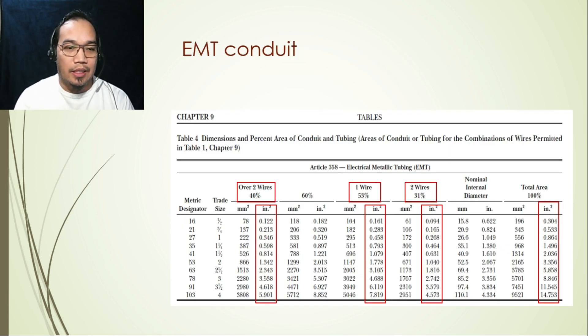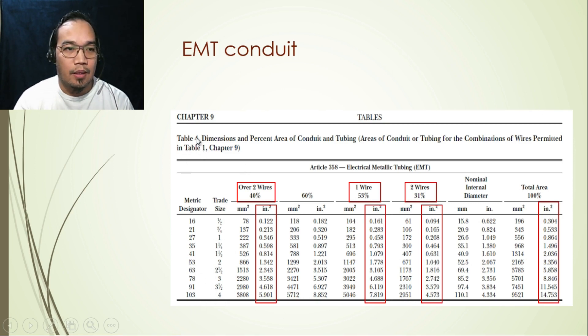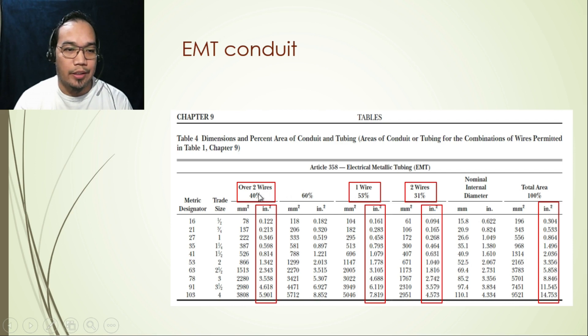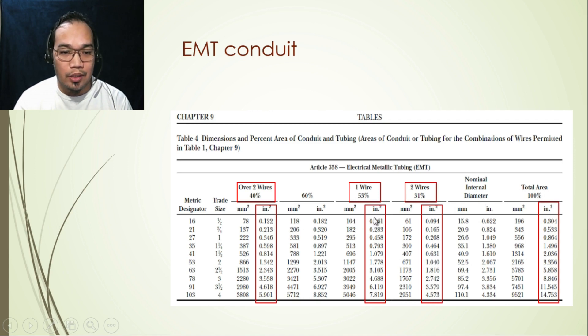This is consistent with what was explained in the table. Here is a sample table for EMT conduit used in NFPA 70, showing the different conduit sizes: 1/2 inch, 3/4 inch, 1 inch, and so on. As discussed, for one wire you can use 53% of the total area, for two wires only 31%, and for more than two wires only 40% of the total conduit area.